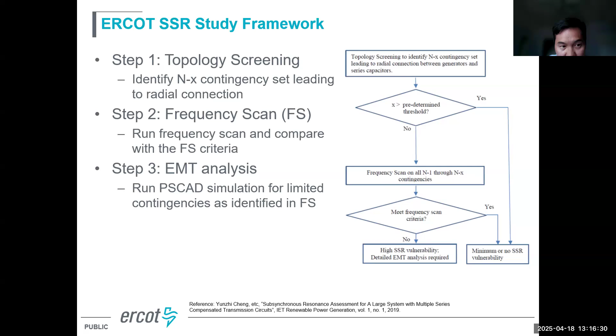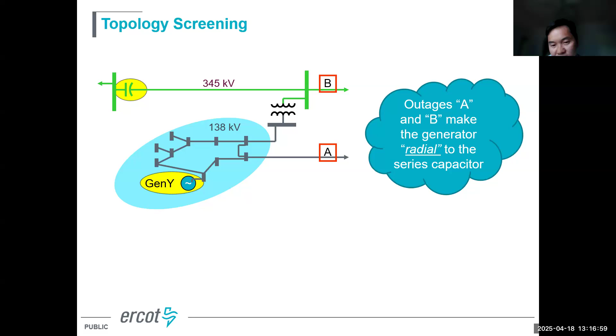The topological scan is pretty straightforward. We basically count outages for the radial connection. In this simple example, if you trip line A and line B, then generation Y will become radially connected to the series compensation. Actually, most of the time we can eyeball the contingencies or outages for radial connection, but sometimes the network is complicated. So we propose an algorithm based on the classic max-flow min-cut theorem to find the minimum X that leads to radial connection. Like in this example, if we trip the double circuit between bus 3 and bus 5 and the single circuit between bus 4 and bus 7, then under this N-3 condition, this generation will be radially connected to the series compensation.